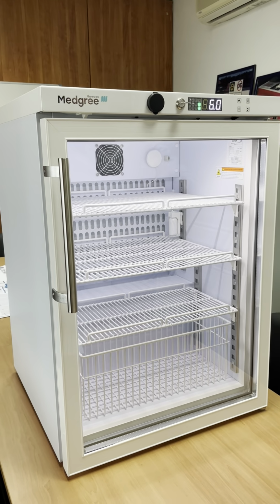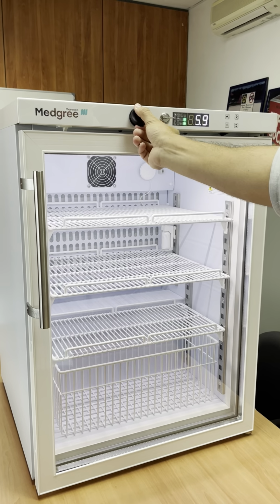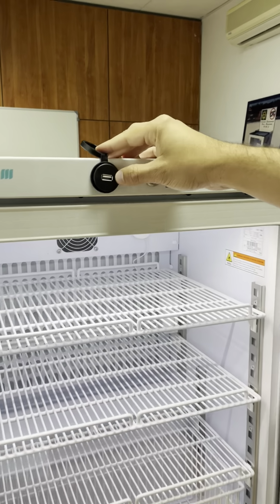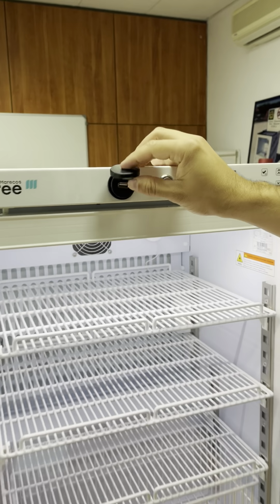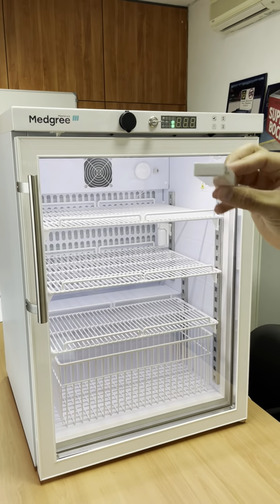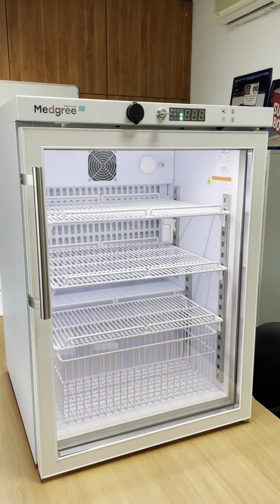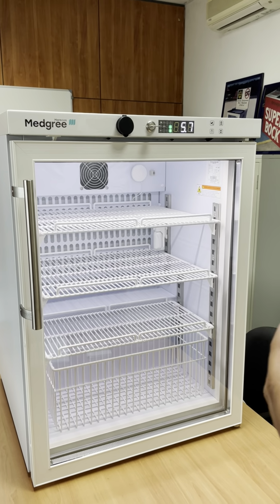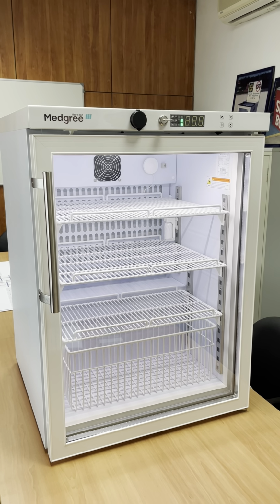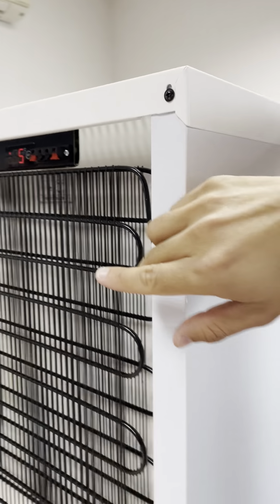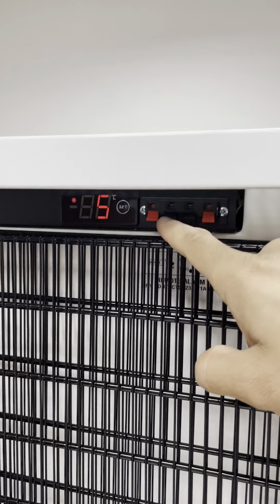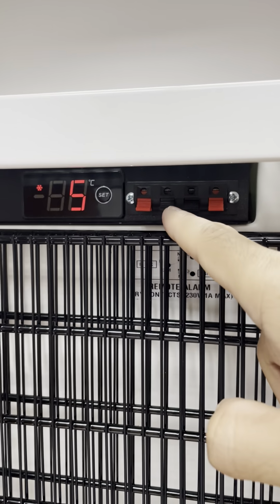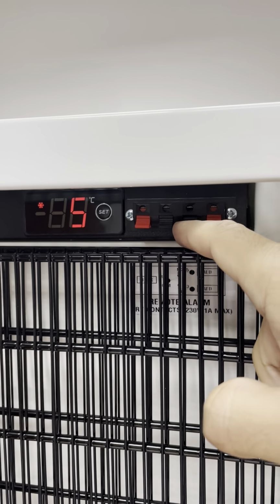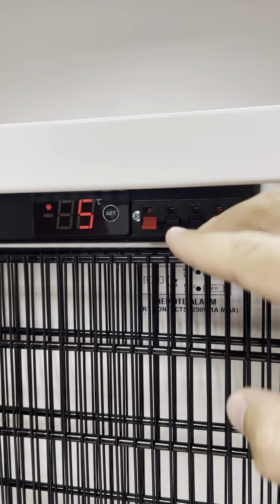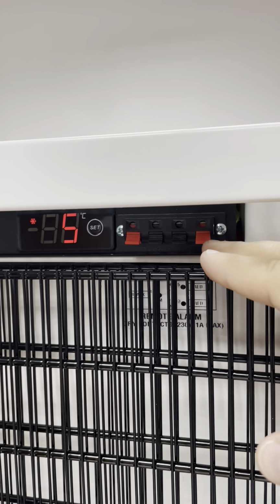So important features about this. So you have the key, you have the USB for retrieving all the data that you can have. All the equipments come inside with a USB drive inside the box. So the MEDGREE USB drive that you can use them to retrieve the data. Then here on the back you have the connections, tension-free connections for remote alarm. If you want to connect the equipment to the alarm system of your clinic or hospital, you just connect the cables here, and you have the tension-free contacts for remote alarm.